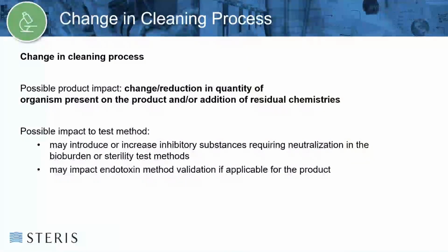The change to a cleaning process has the potential to change the quantity or types of microorganisms present on the product. It can also lend residues of the cleaning chemistry. This could impact organism recovery in the test method and require neutralization for either bioburden or sterility methods. Change in organisms could also impact endotoxin levels and existing biocompatibility studies.